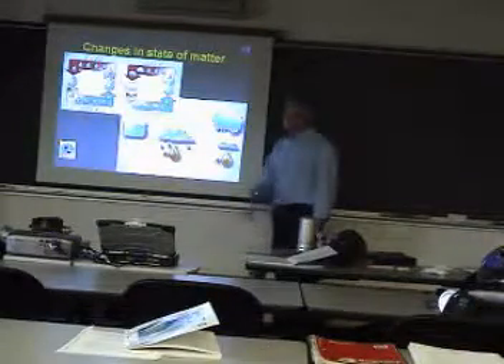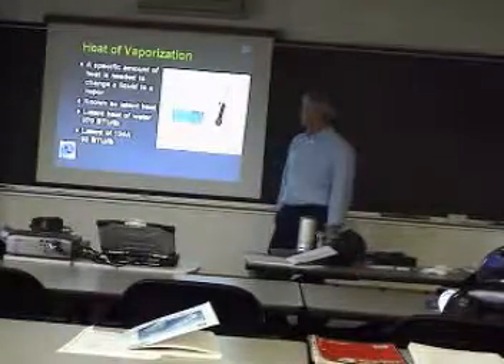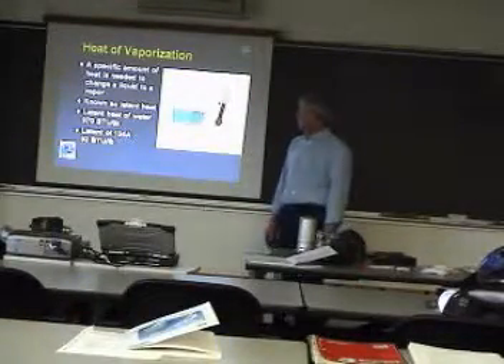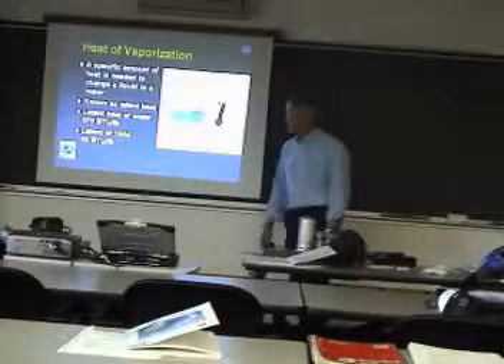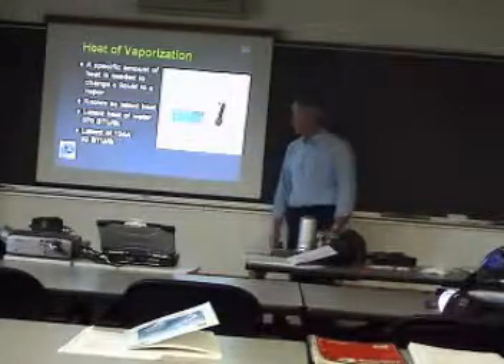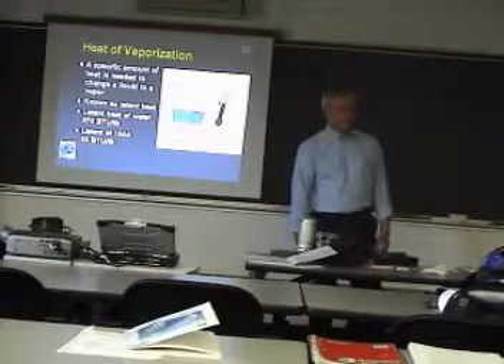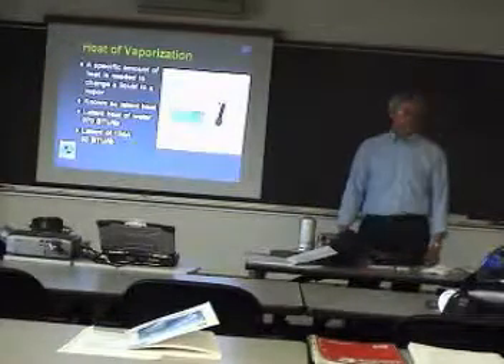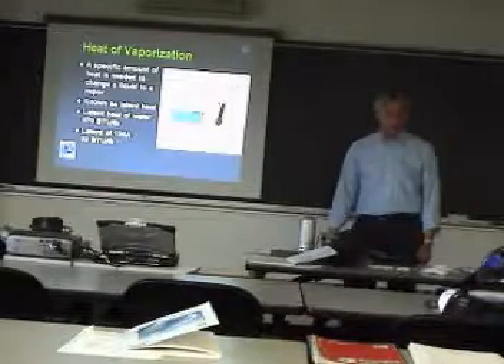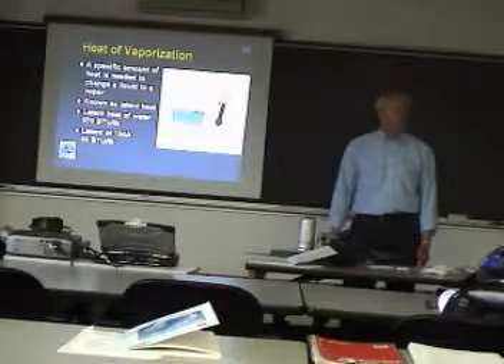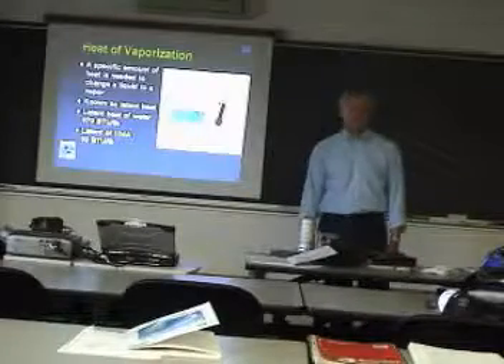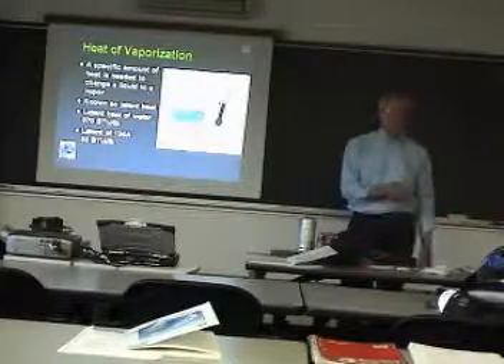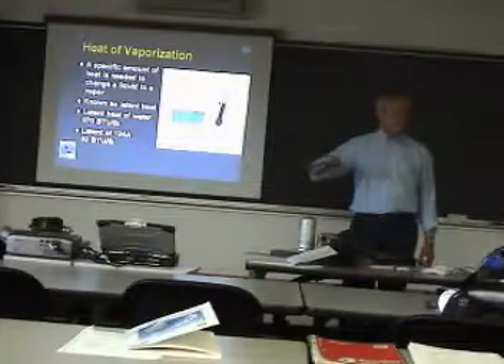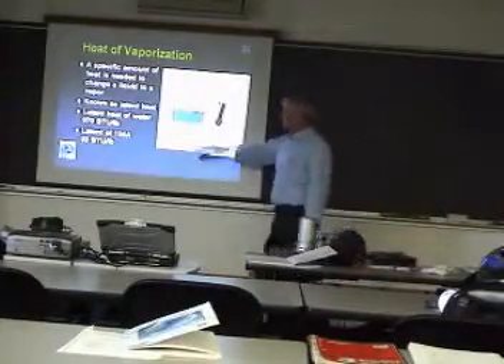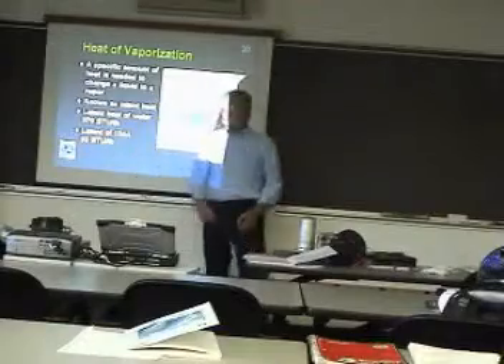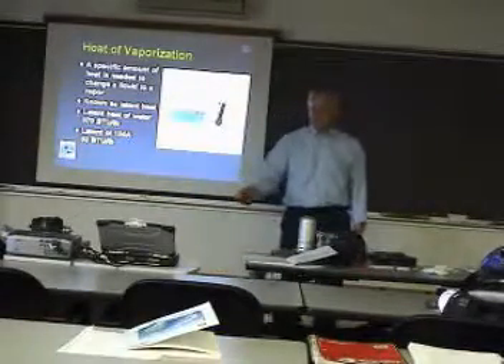The whole idea is to get that change of state to occur. You guys can review that. We talked about this a little bit. Latent heat of water, they're saying 970 BTUs per pound. R134a, to make that change of state, is around 93 BTUs per pound. So, not as much as water, but a lot more than it takes to just absorb heat energy from its freezing point up to its evaporation point. We need to have it do this. We need to have it evaporating for it to be effective in absorbing heat energy.